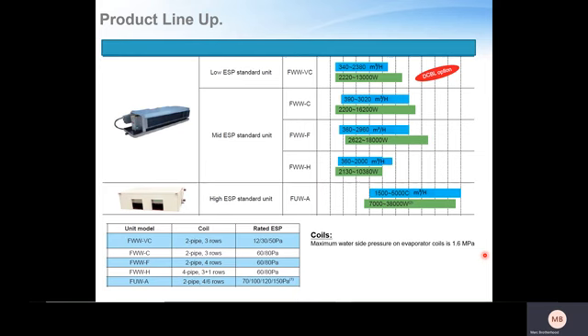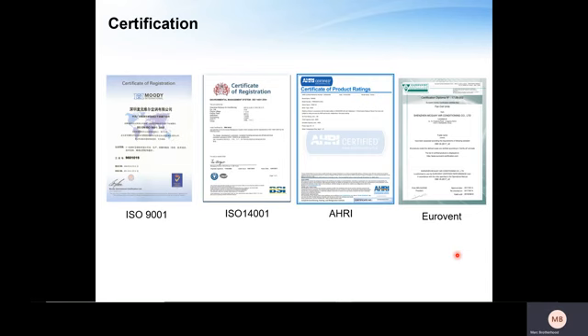And the ESPs, generally just a background for ESP, it is your external static pressure. That is the work your fan has to do against static air molecules in the ductwork. So that is the work that the fan has to do to overcome air molecules that aren't moving, as well as friction on the ductwork. So generally, as a rule of thumb, the pressure drop in a low velocity ductwork system is normally around 1 pascal per meter. So here you can see the high ESP units can really do on high fan speed quite a lot of work against static air molecules and friction and bends of ductwork. There's also some very good certification, ISO 9001, ISO 14001, the AHRI certified, as well as Eurovent certification for these fan coil unit ranges.